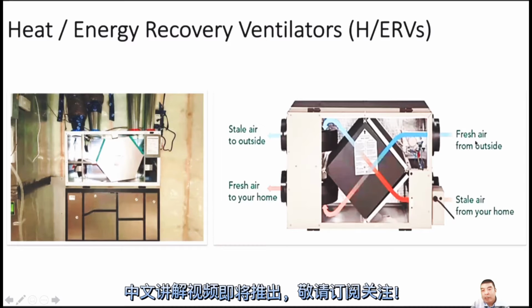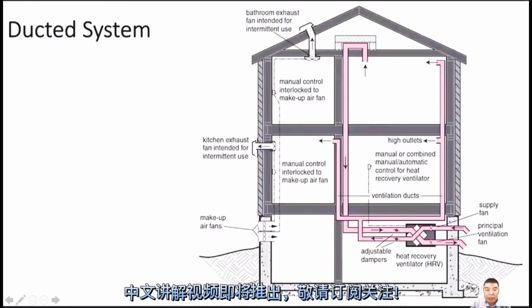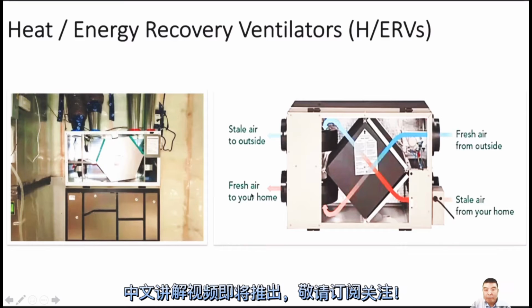Now we know this is the fresh air from outside. That means this pipe needs to be insulated, because it just sucks in cold outside air. If it is not insulated, there may be lots of condensate water. So all the pipes connected to the outside need to be insulated. The fresh air is sucked in from here, goes through the filter and this heat exchanger, passes through here and blows out from here.